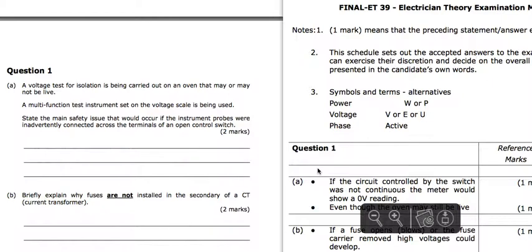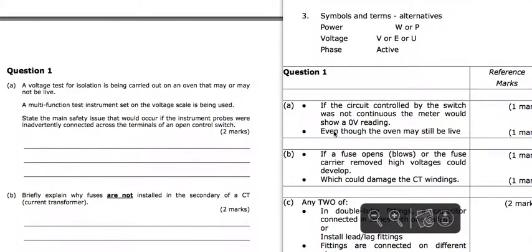And if you go across a switch that may be open circuit somewhere within that control circuit, you're going to get a 0 volt reading, even though the oven may still be live. So we can't trust any voltage readings across a switch.